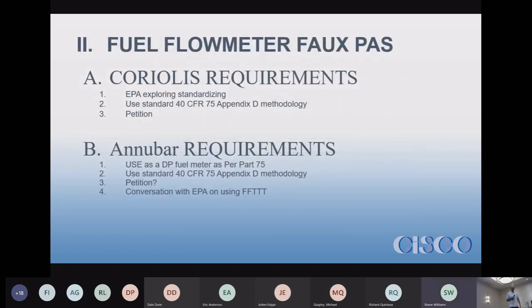So, fuel flow meter stuff. Every year, new fuel flow meters come up. The Coriolis meter is one of the most common ones that comes up with issues from sites that switch to it. And it's one of the most awkward ones because the EPA acknowledges, at least in interactions at conferences, that they don't understand why these haven't been standardized. And every time you petition, the petition goes through.